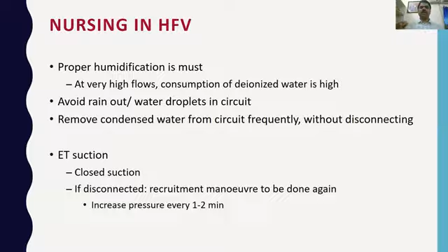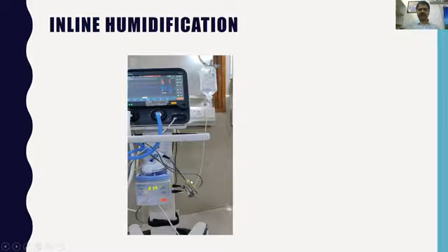So this is what I was just mentioning. Inline humidification option also is there. So if you want to, for example, put this deionized water into the humidifier chamber, don't disconnect the humidifier chamber. Sometimes some of the nurses do that, but you use inline humidification, so that when this water is getting depleted, it will get automatically filled up.